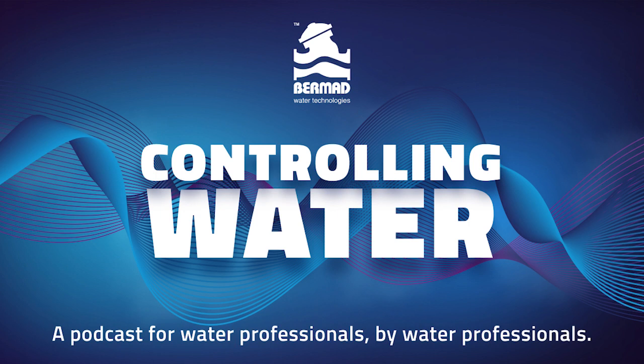So can you tell me about the purpose of the training facilities? Water companies don't like you training users or operators on their own network, because if they get it wrong, you generate water hammer, you can fatigue the pipe, stress it, and cause a failure. A lot of the time these products are in valve pits below ground — very hard to get to, in dangerous locations that require documentation and training, because you're in a confined space needing certification and breathing equipment.